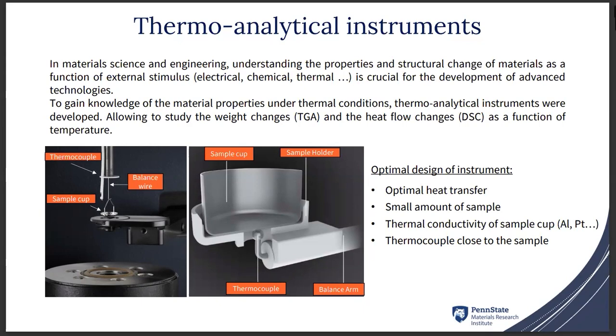So the TGA allows you to study the weight change as a function of temperature, and the DSC allows you to study the change of heat flow as a function of temperature. Here is a picture of the design of a TGA on the left and a DSC on the right, and we can see there is a lot of similitude between those two designs. First of all, both of them have a sample cup. They are both attached to a balance wand, with a balance wire for the TGA and a balance arm for the DSC. And in both cases, the thermocouple is either very close to the sample or touching the sample cup.